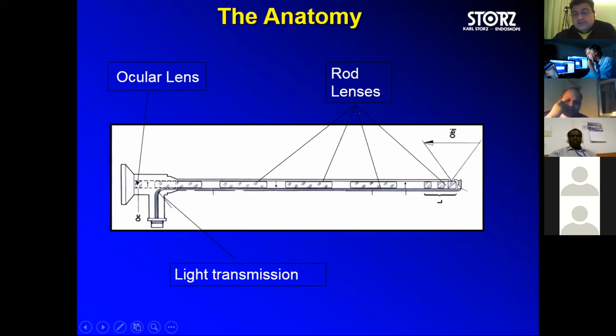If you see the tip lens of the endoscope, it is slightly inside the metal sheath. Why? Because if it drops vertically or hits some structure, the tip lens should not be damaged. Plus, we are using a sapphire glass lens. The sapphire glass lens has the property that it is anti-scratch in nature, so you will not have any scratches. I will tell you in a subsequent slide how to clean and maintain the endoscope to have a fantastic image, even if the scope is used for a very long time.